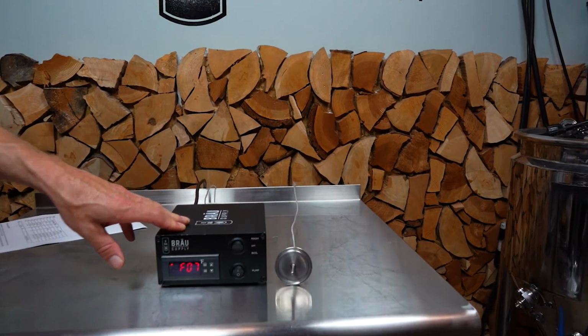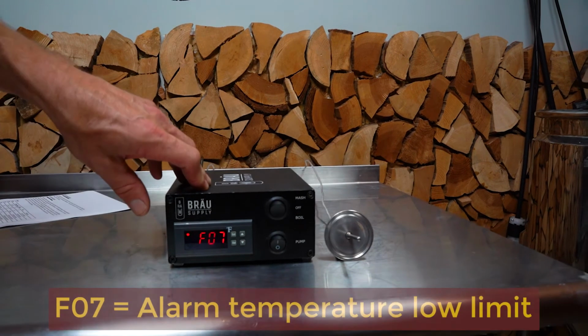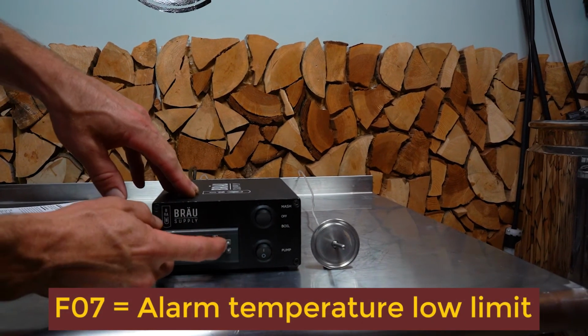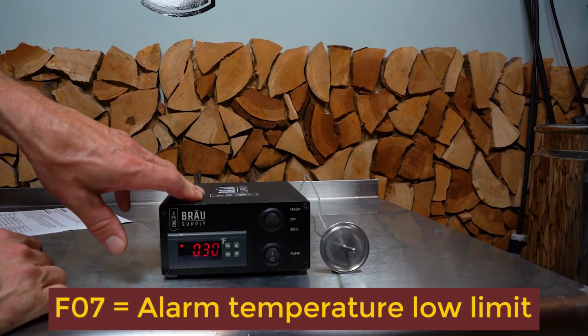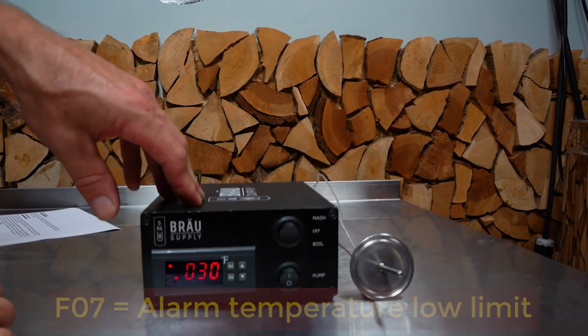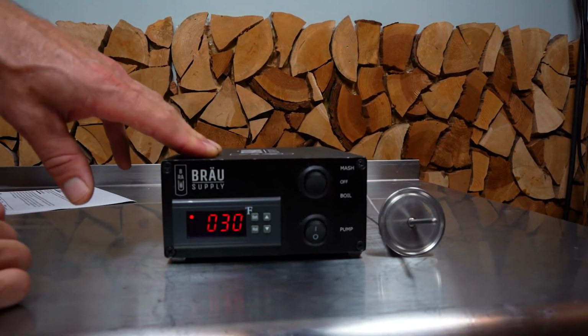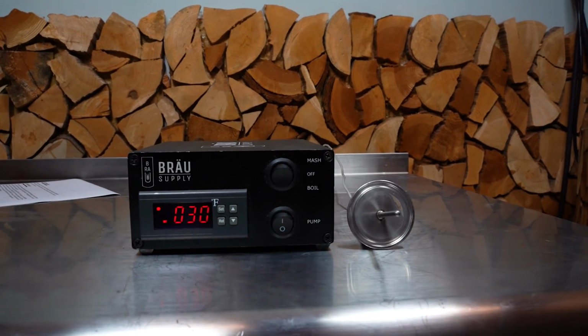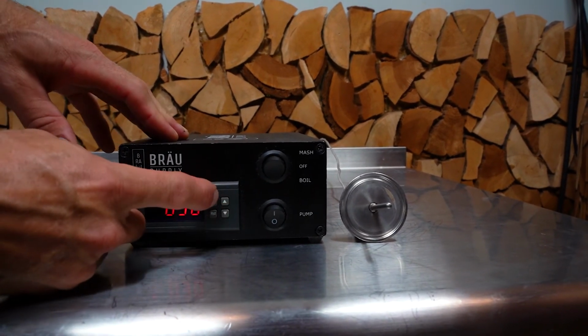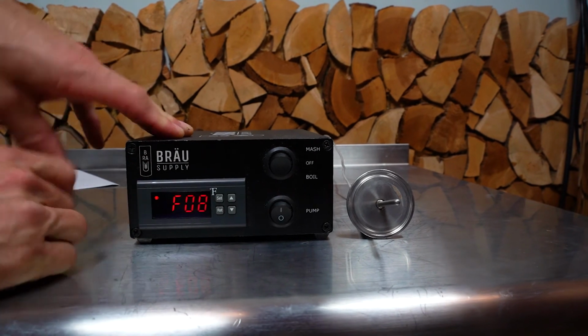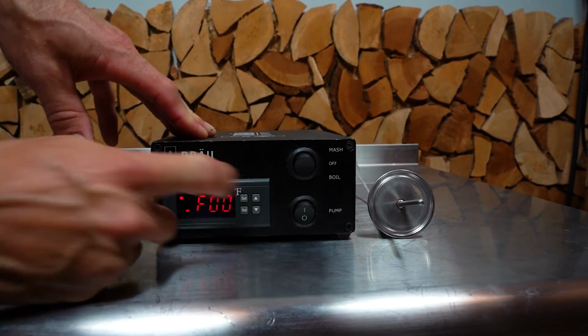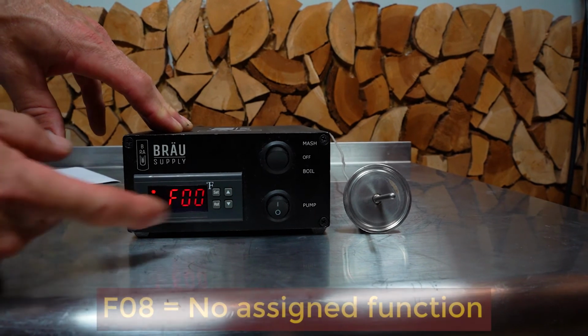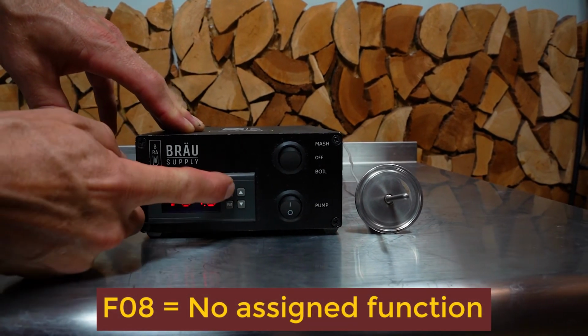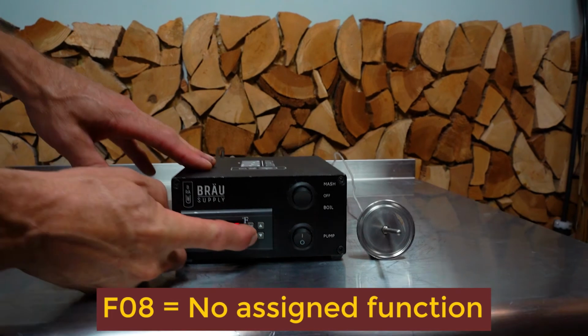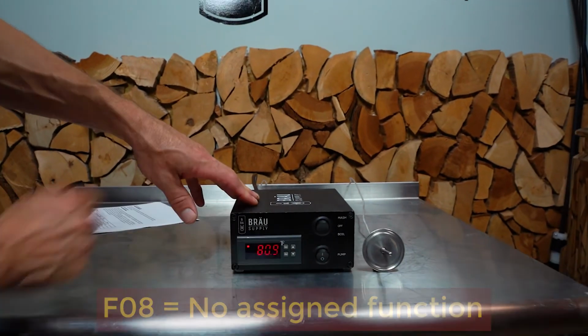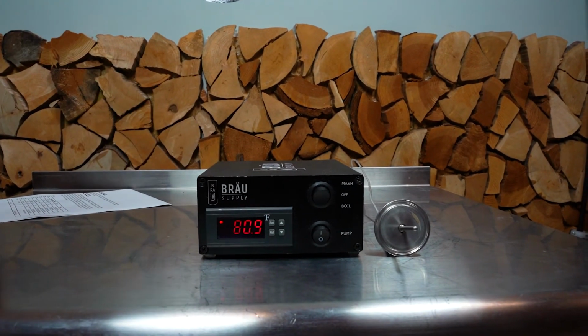F07 is alarm temperature low limit. So again, its default is set pretty darn low. That's 30 degrees. I don't really bother with it. I keep it nice and low because it's generally not needed. And then we've got one more, F8, and that really, it hasn't been assigned anything. So you can just bypass that and it brings you to F0. So that's that. And I believe if we just press reset, yes, it worked. It goes back to the original screen.